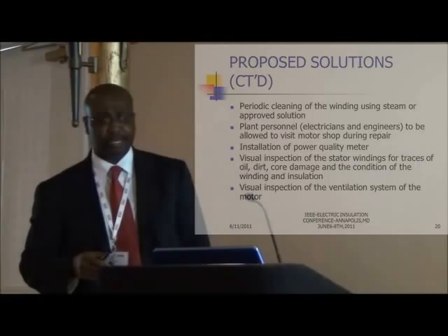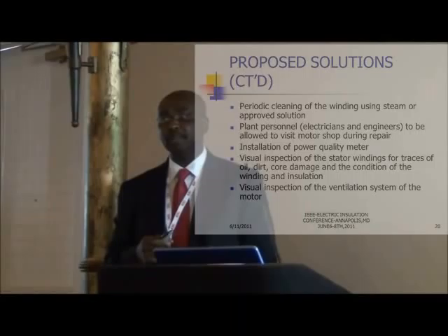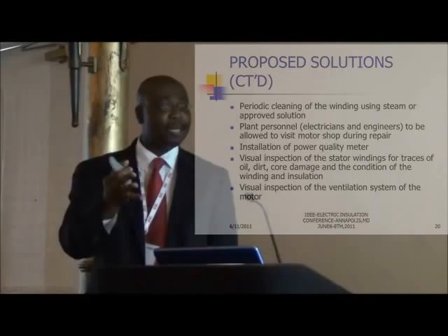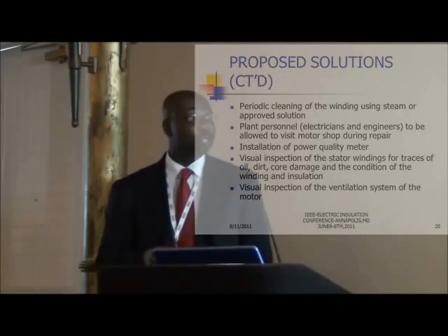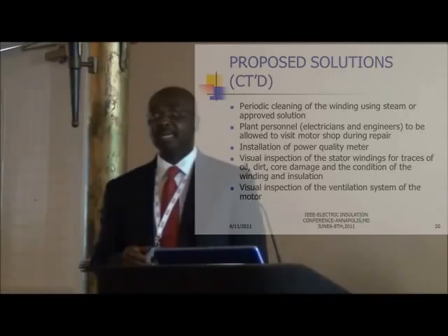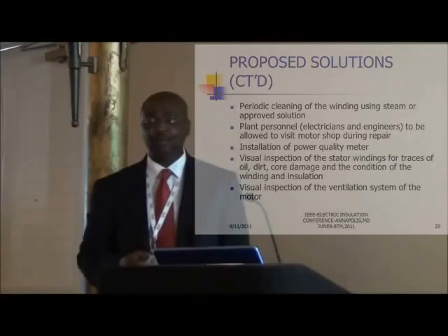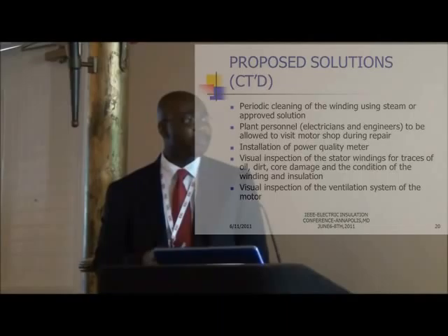We also created a PM for inspection of stator windings in the slot for tightness when the rotor is removed, and inspection of end winding support for tightness. We found that electricians only knew how to perform traditional megger testing but did not know how to interpret the results. We trained the electricians on how to interpret insulation resistance testing and developed criteria for evaluation. We also installed power quality meters in the switchgear to monitor voltages and currents and provide early indication of motor issues.